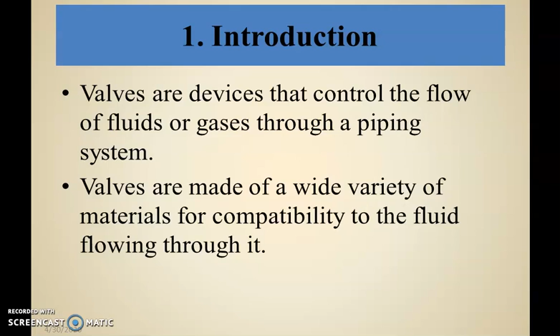The valves are made up of a wide variety of materials for compatibility with the fluids flowing through them. The material of construction of the valve should be compatible with the fluid. If you are using H2SO4 as a liquid and a stainless steel valve, the H2SO4 will completely dissolve the stainless steel, so it is not compatible. Stainless steel valves are not compatible with H2SO4, so a variety of materials must be used for compatibility with the fluid flowing through it.